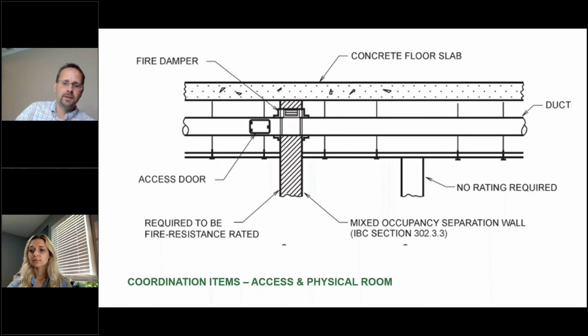There's also, we've had several clients who've gone through and asked us to review their code plan and review their building to see if there's any dampers that are no longer needed by the current codes. And then they decommission those, because over the years, dampers get applied in a way that's above and beyond what the code requires, either from good intentions and misunderstanding the code, or a code official who didn't quite understand what they were enforcing. And so it's been worth it for them, the amount of time and money they spend testing these on a regular basis, to decommission dampers that are not required by code and that were put in for whatever reason.